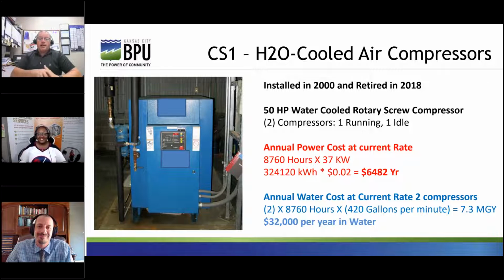So as I said, the plant was designed to have 2 water-cooled 50 horsepower rotary screw air compressors for redundancy. The operation mode for 18 years was 2 compressors, 1 in service and 1 in standby. However, both ran with water through them regardless of the running state, 24/7, 365 for cooling. The manufacturer of these compressors estimated 7 gallons a minute, plus or minus, needed for cooling of the compressors. Water used calculations for the 2 compressors.